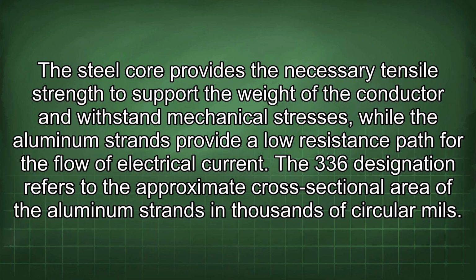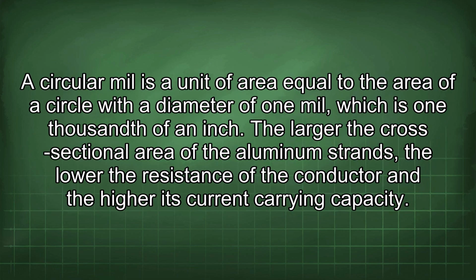The 336 designation refers to the approximate cross-sectional area of the aluminum strands in thousands of circular mils. A circular mil is a unit of area equal to the area of a circle with a diameter of 1 mil, which is 1/1000th of an inch.